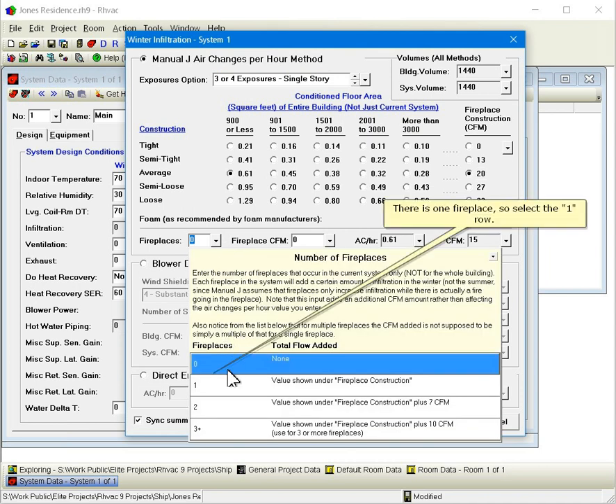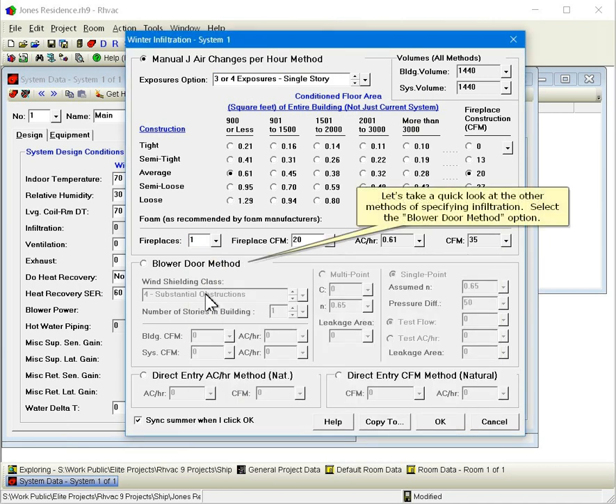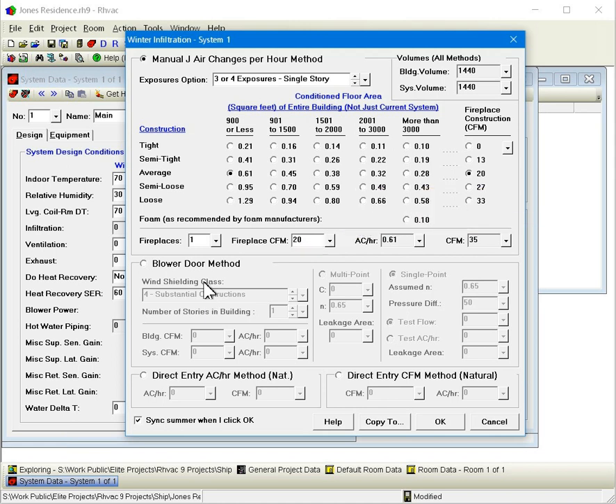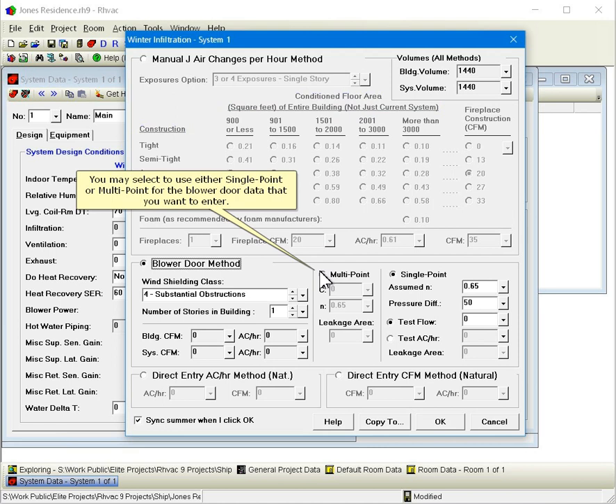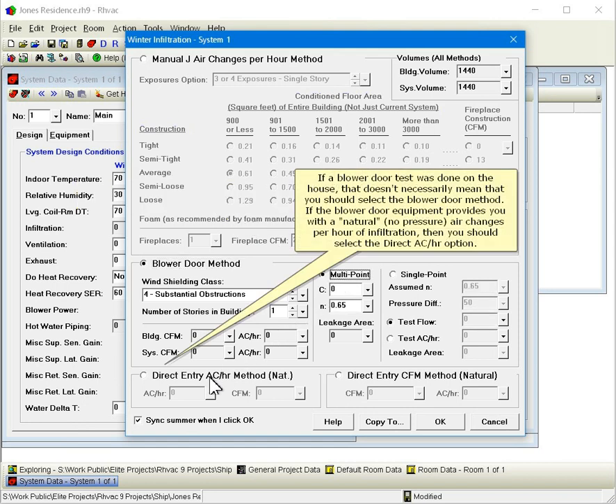Let's take a quick look at the other methods of specifying infiltration. Select the blower door method option. You may select to use either single point or multipoint for the blower door data that you want to enter. If a blower door test was done on the house, that doesn't necessarily mean that you should select the blower door method. If the blower door equipment provides you with a natural, no pressure air changes per hour of infiltration, then you should select the direct air changes per hour option.